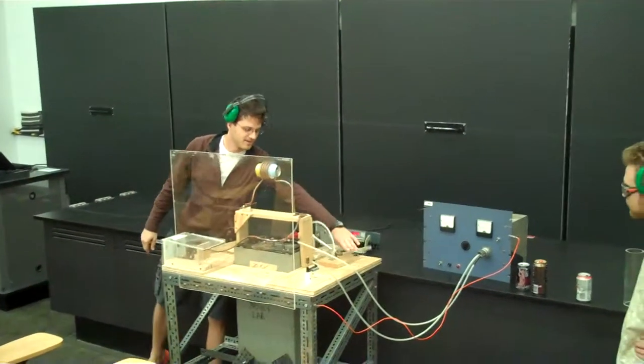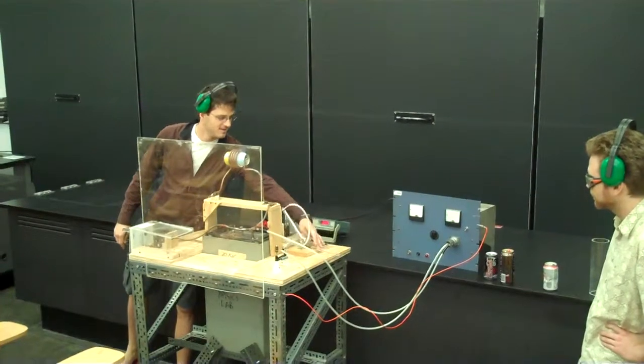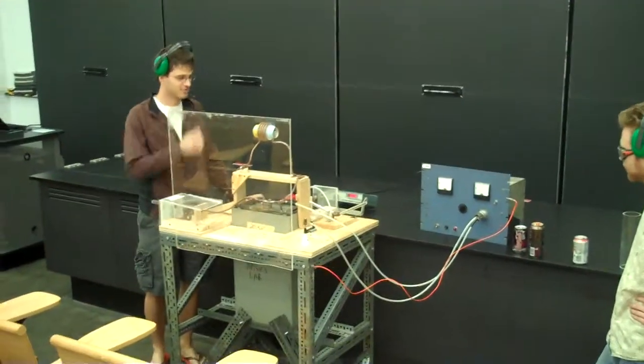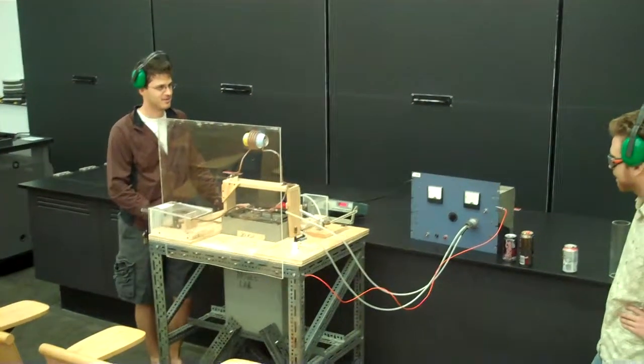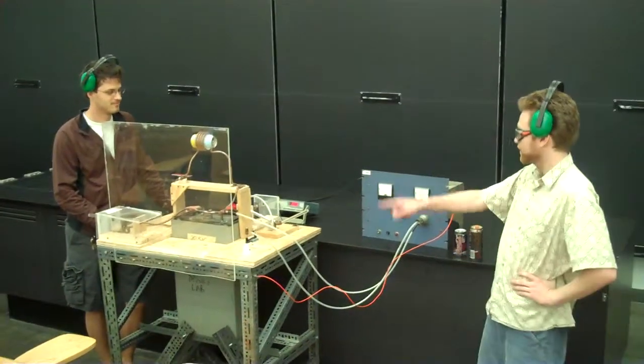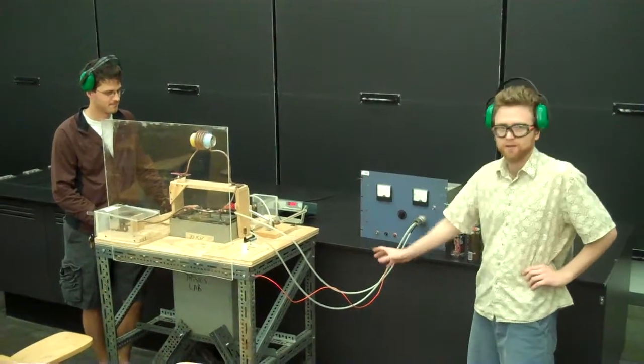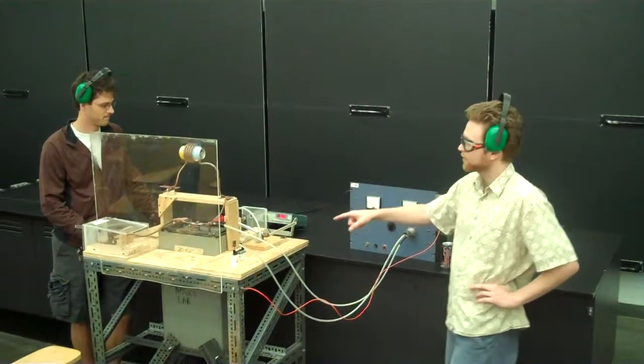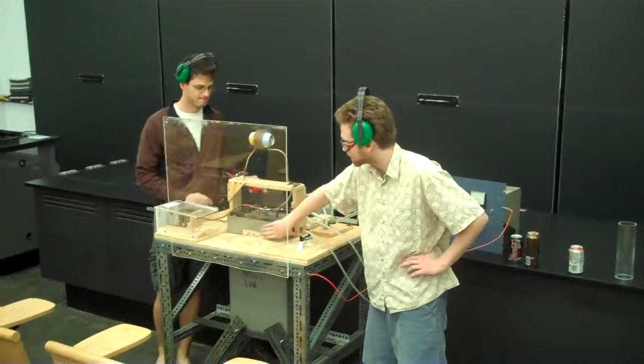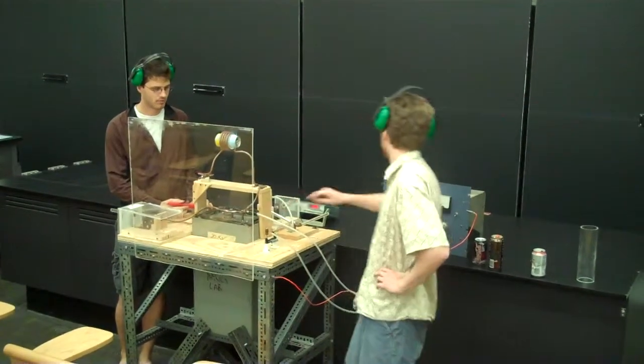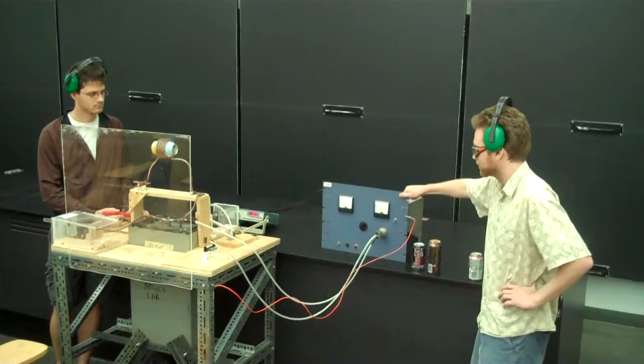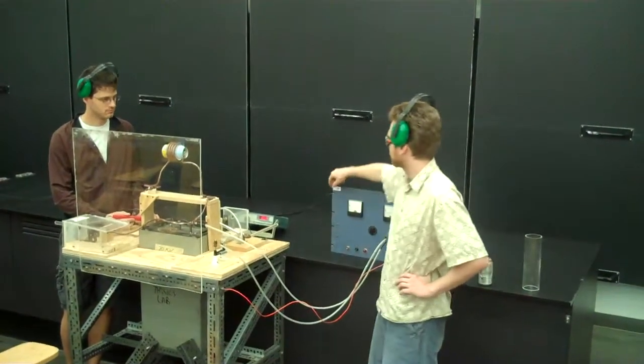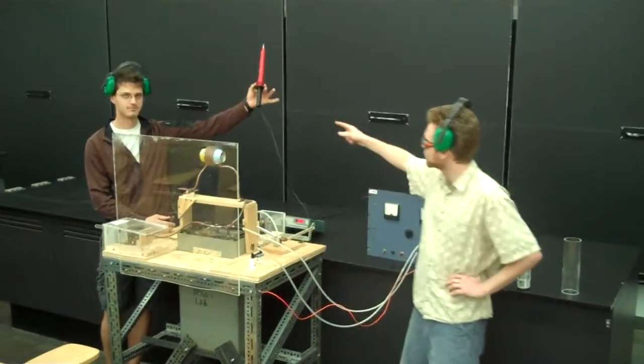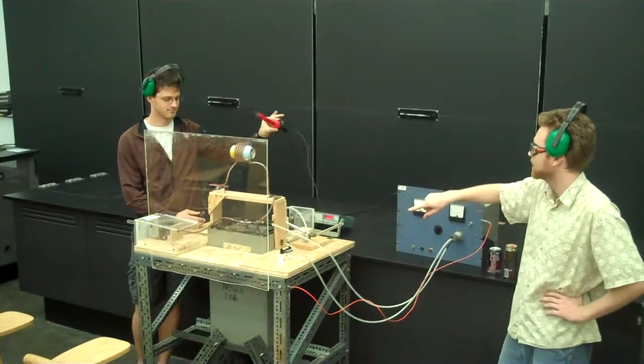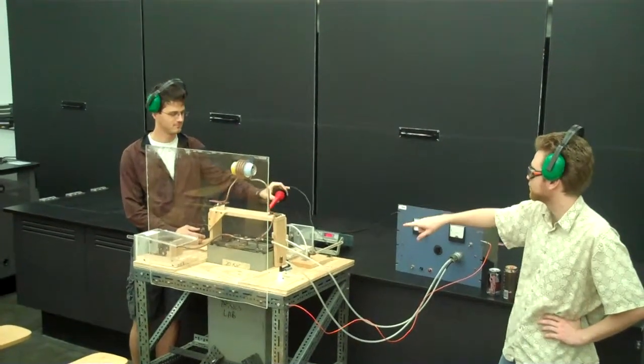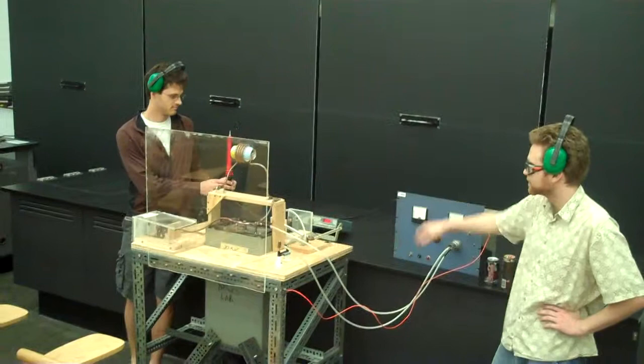This is the charging mechanism here, and this is the high voltage charger, which requires some care. Notice that we've grounded the chassis of the cart, and it's grounded to the negative terminal, which is the outside chassis of the capacitor. And we've grounded that to this high voltage supply, as well as the ground cable for the probe, which we're going to use to measure the charge on the capacitor, stepped down by a factor of 1,000, so we can use an ordinary multimeter.